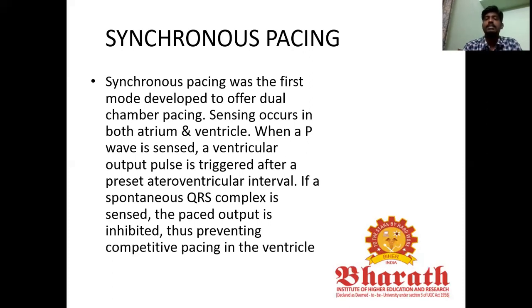When a P wave is sensed, a ventricular output pulse is triggered after a preset atrioventricular interval. If a spontaneous QRS complex is sensed, the paced output is inhibited, thus preventing competitive pacing in the ventricle.